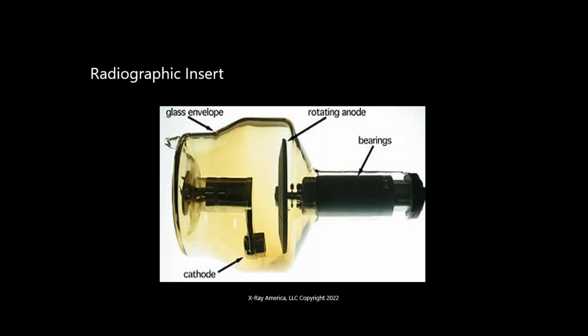So one of the big challenges with X-ray tubes is because they're in a vacuum, rotation. This target is going to spin, but whatever the coating is on the ball bearings, or whatever bearing you're using, when you put it together, that's what you got. Because in this kind of X-ray tube, you can't lubricate. And this is one of the main end-of-life failures on the tube.